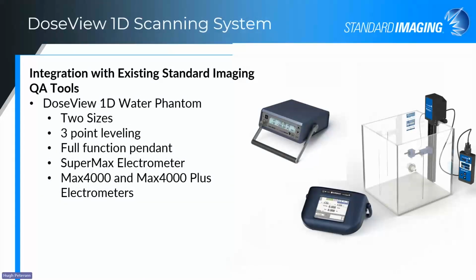As I mentioned, the software itself, which I'll get into in a second, also runs our 1D Water Phantom, so the same software runs both, with a full function pendant and 3-point leveling on this phantom as well. Two size tanks, so you've got a smaller tank and a larger tank, depending on what your QA needs are for your monthly checks. And it integrates with our Supermax electrometer and our Max 4000 and Max 4000 Plus electrometers. So if you have any questions on that, we can certainly assist you there too.